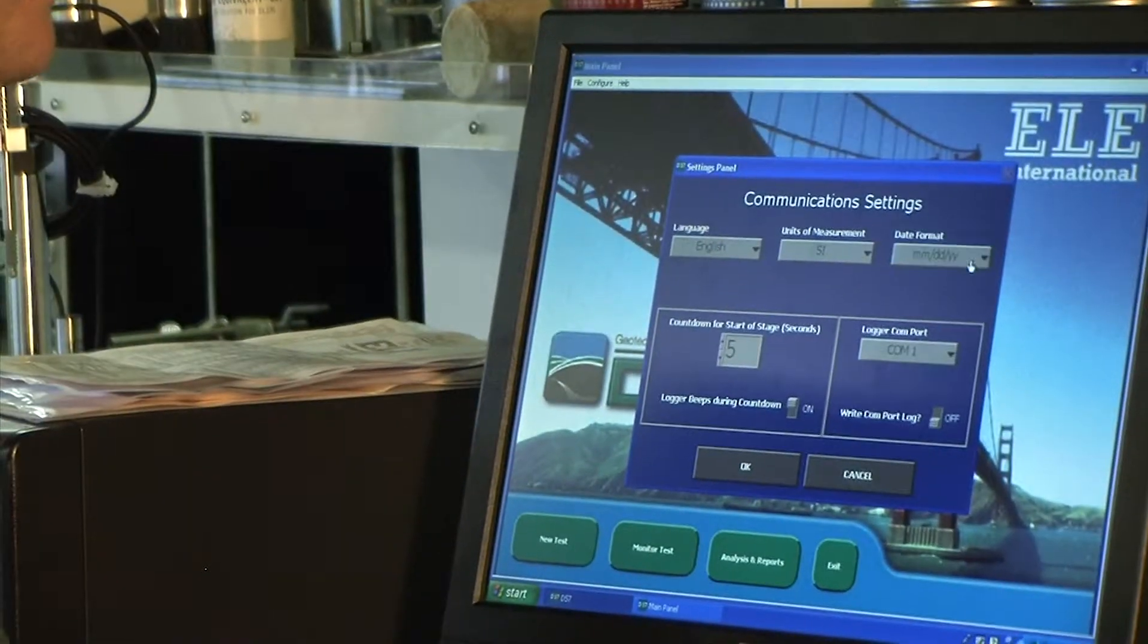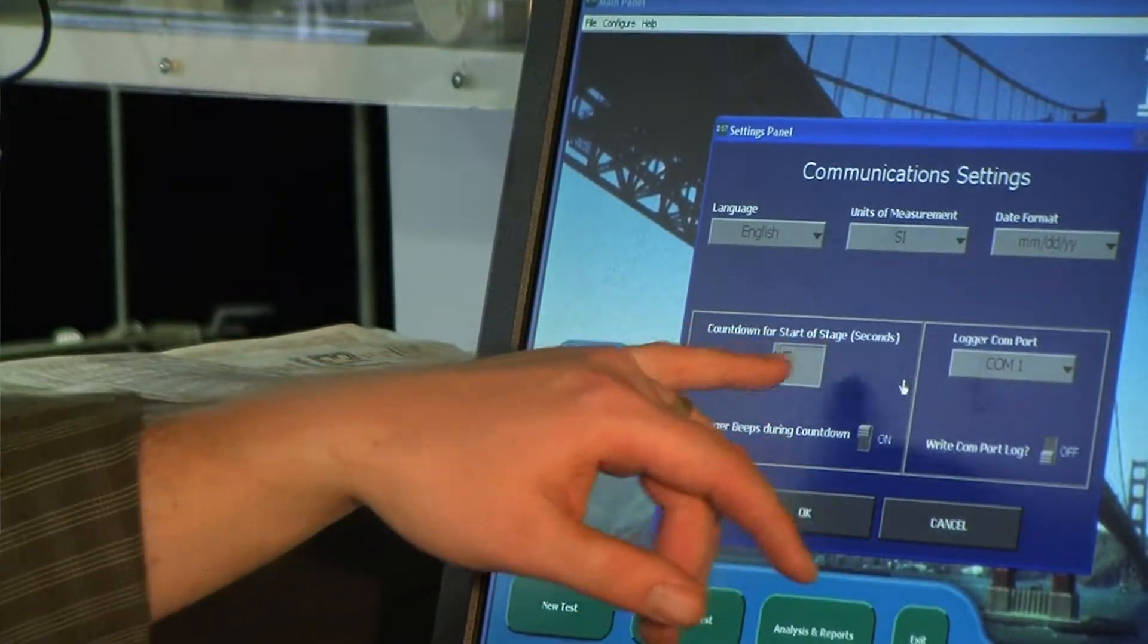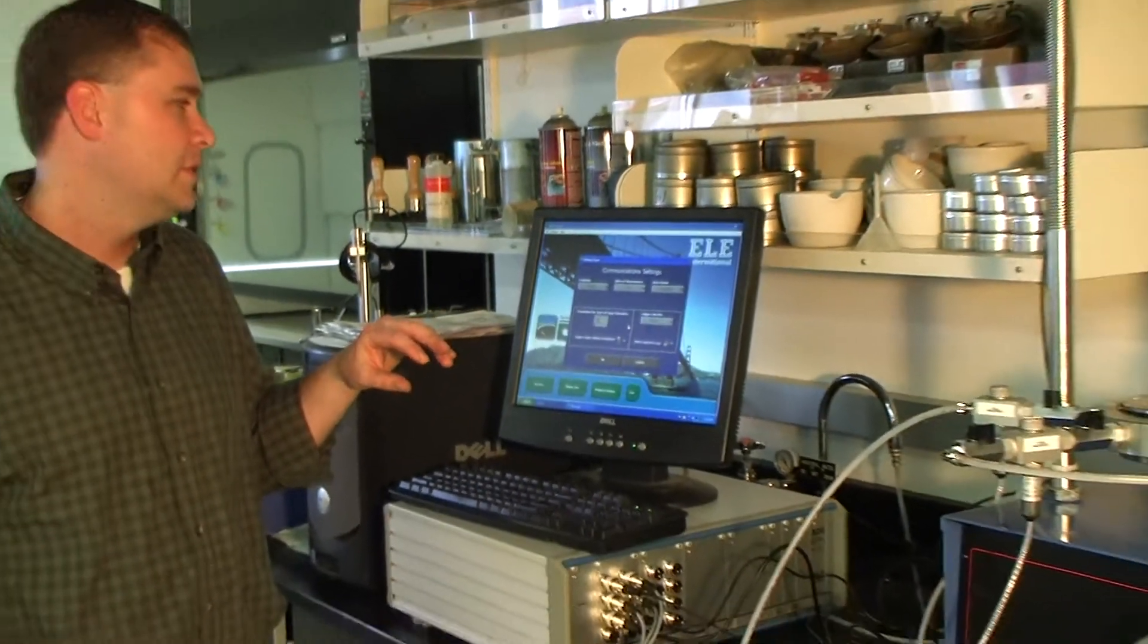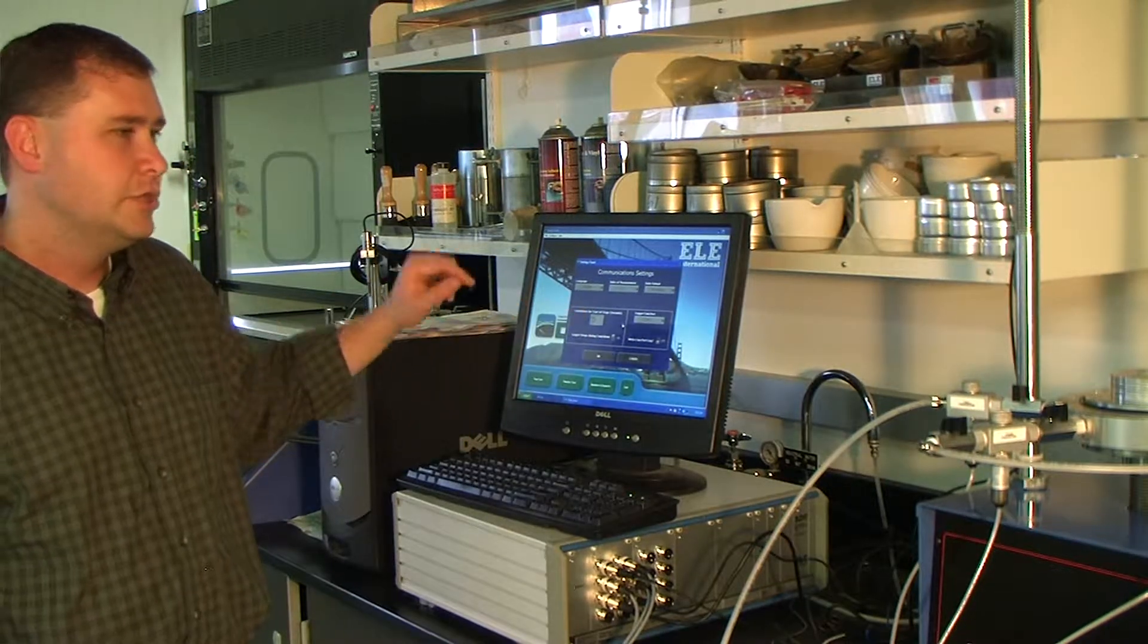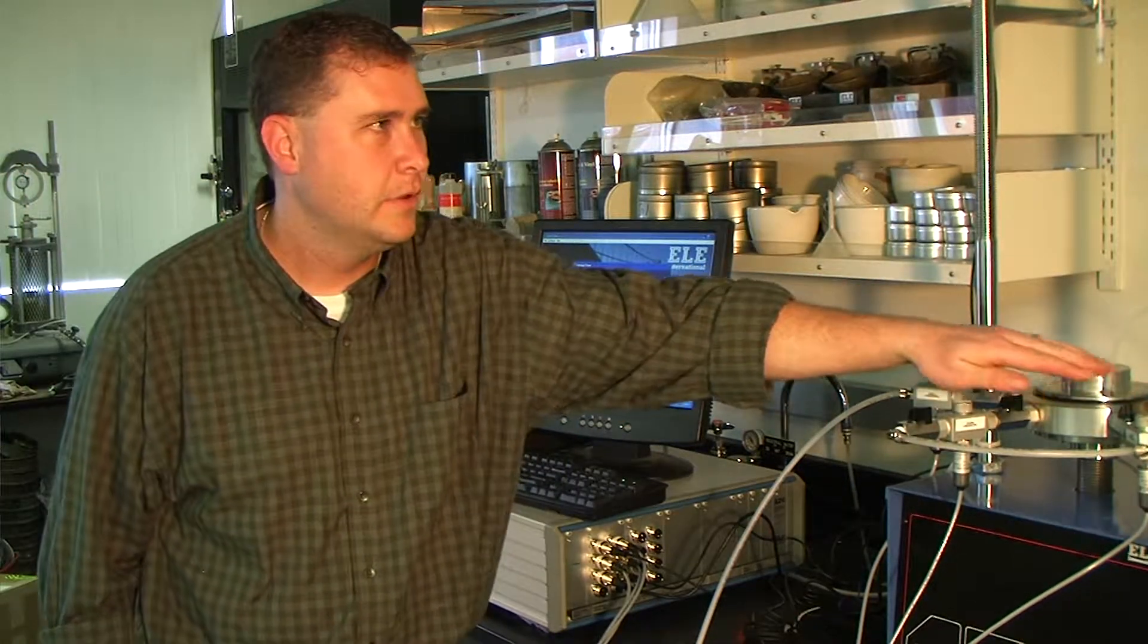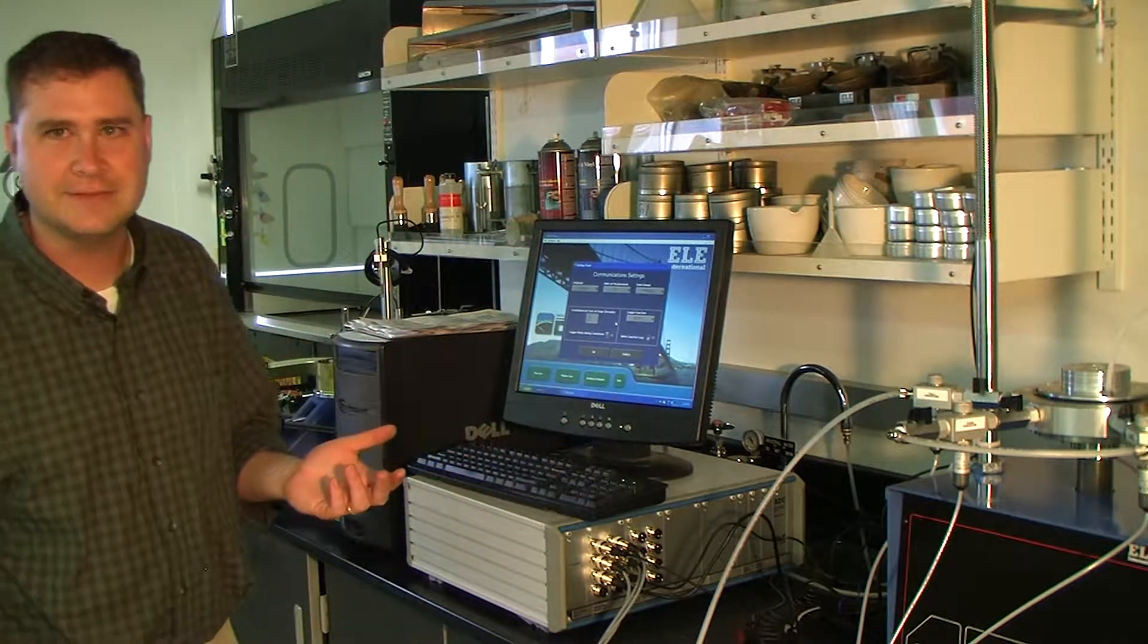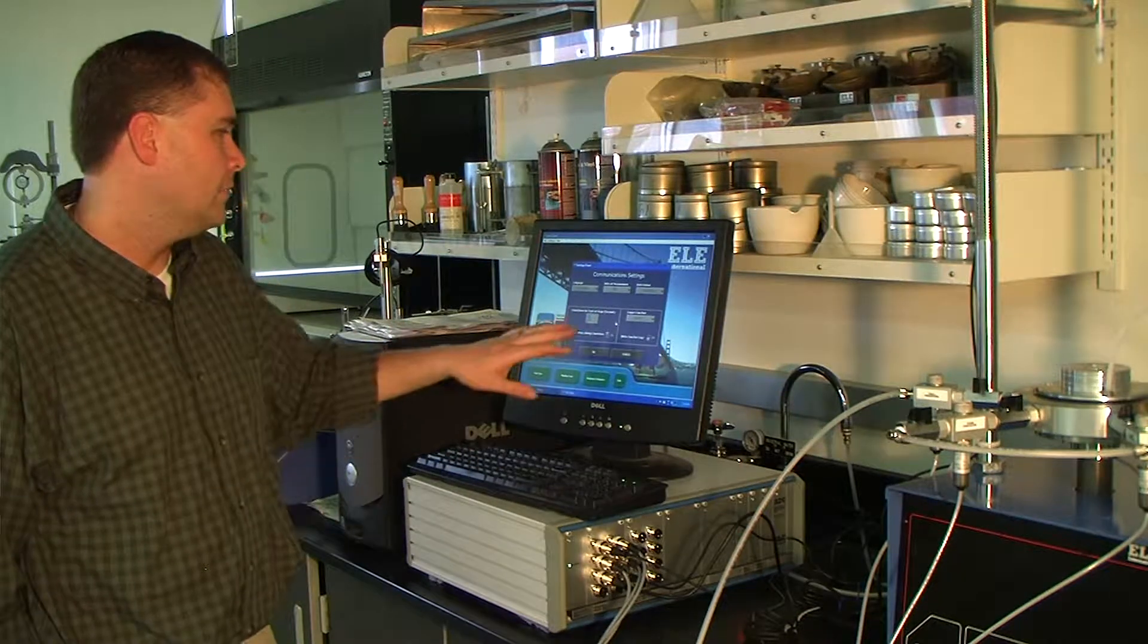The date format is just British or American. Here we have something called the countdown for the start stage in seconds. You can turn it on or off. What this does is the ADU provides beeps, loud noise beeps to give you time that when you push a start button on the screen, it gives you that amount of time to walk over and actually perform the task it's asking you to perform. Whether it be open this valve or lower the weight onto a sample for the consolidation or direct shear. Whatever the task is, it gives you time to walk over and perform that task.